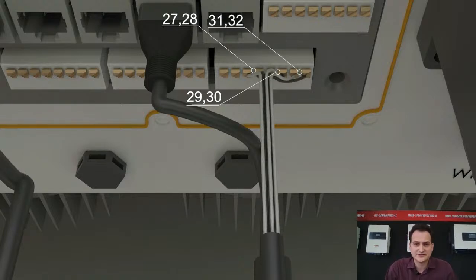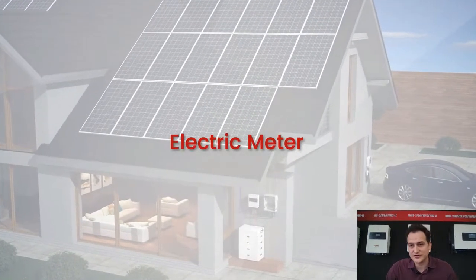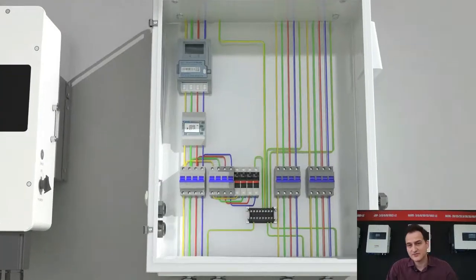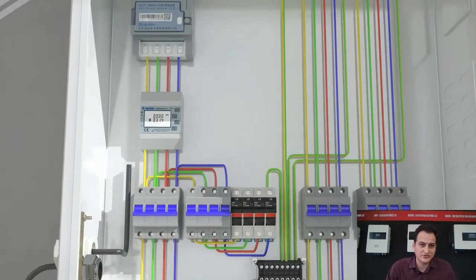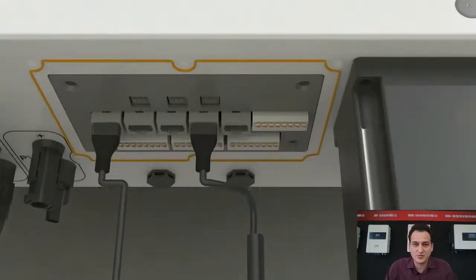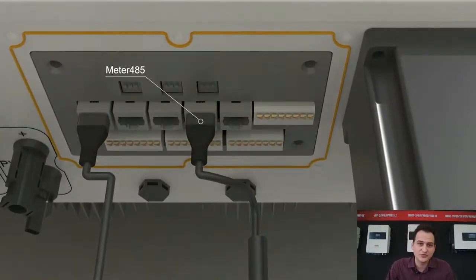So just these 3 CTs, and our inverter will measure what's going to the grid and what's coming from the grid. If we don't want to use CTs, or the distance from the inverter to our measurement point is more than 5 meters, we have to use a meter. The meter we connect to our RS485 port.